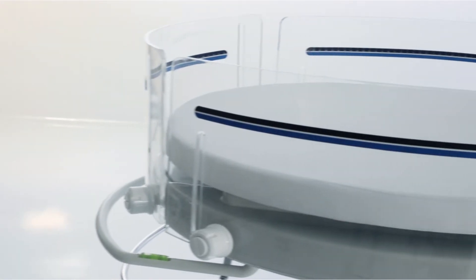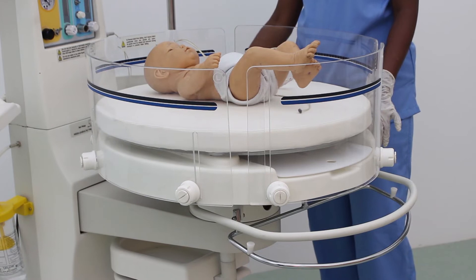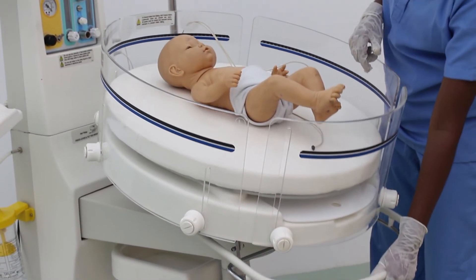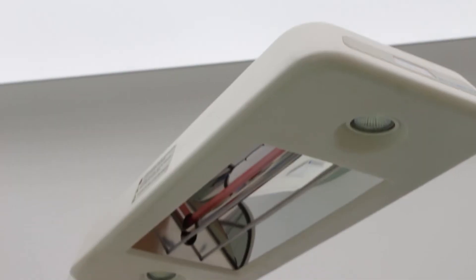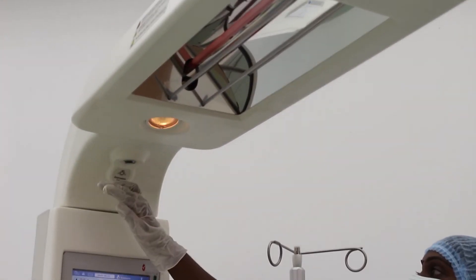The world's first oval-shaped bed by Phoenix Medical Systems is designed to facilitate access in every which way. The bed can be tilted up or down and swiveled or rotated horizontally. The CIC 101 has an overhead warmer unit with temperature sensing done by a thermistor.